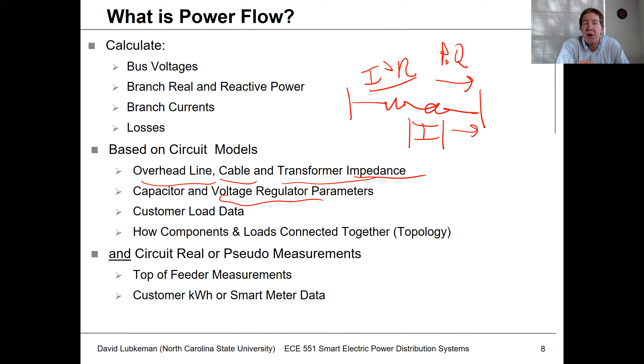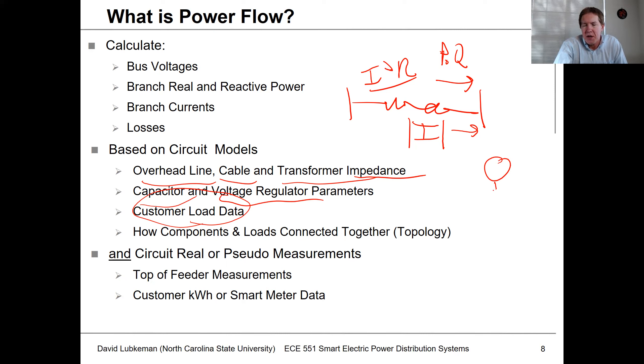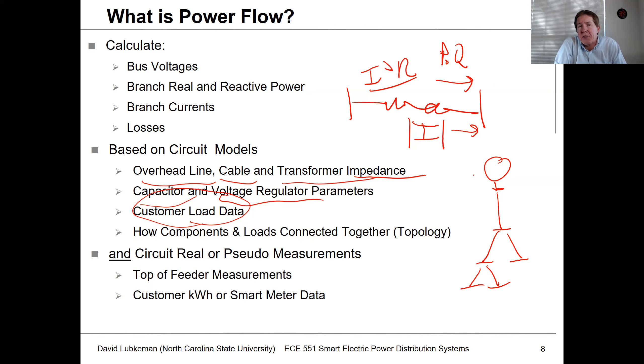Other inputs include information about line voltage regulation, which we talked about in the previous lecture, and capacitor bank locations — whether they're fixed or switched, which we'll cover in a future lecture. We also need customer load data. Since we have a lot of points on a distribution circuit, this is a lot of data to manipulate. We also need topology — that is, how all the different feeder segments are interconnected together. This interconnection is what we refer to as the topology of the circuit.